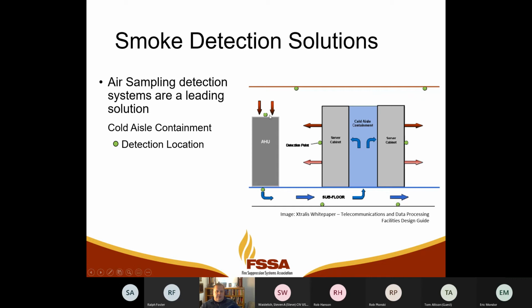Now you see some other ones here, because this is frankly out of an Xtralis white paper, so they want to sell more air sampling, so they're showing it at the CRAC units on the incoming side and the leaving side. But that's okay. One thing that you don't see on this, and this is kind of important, is you don't see detection right here at the ceiling on the cold aisle.